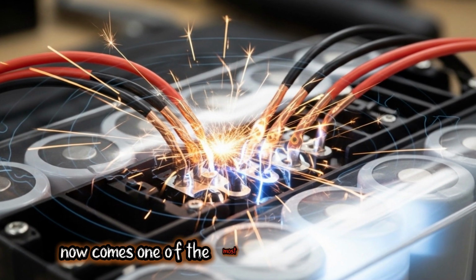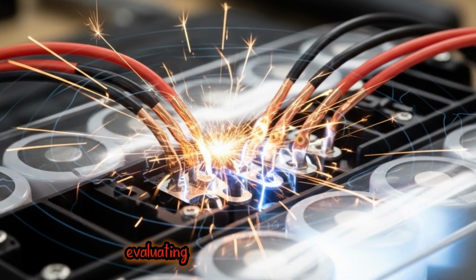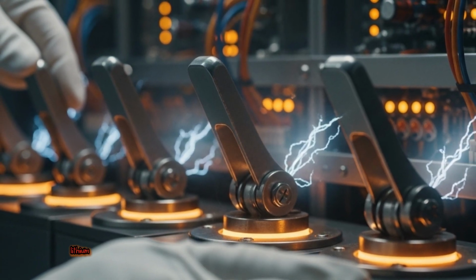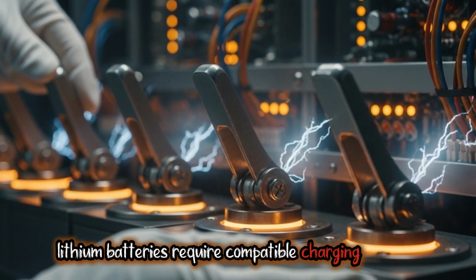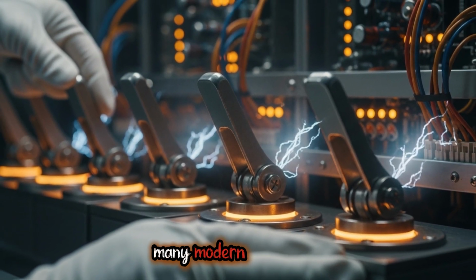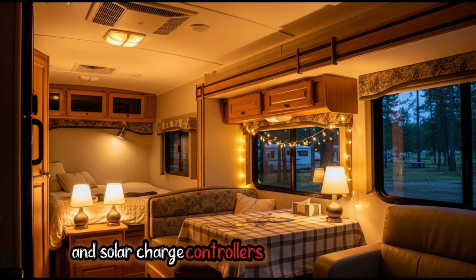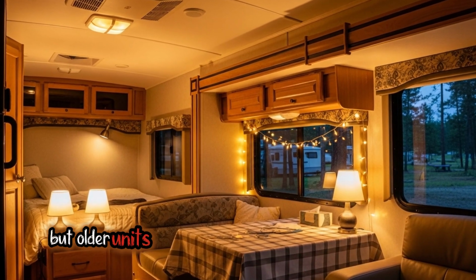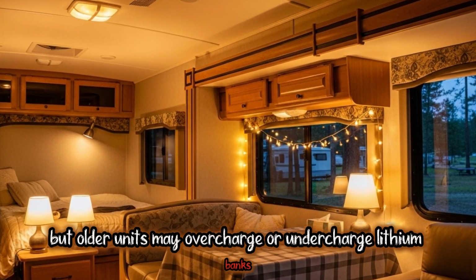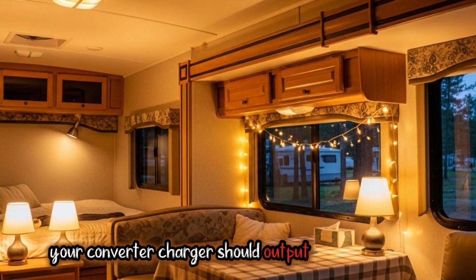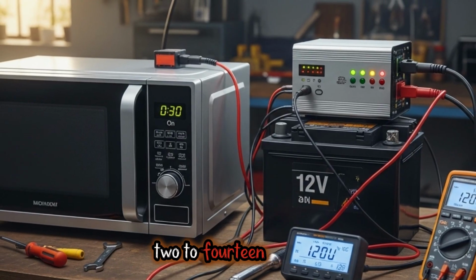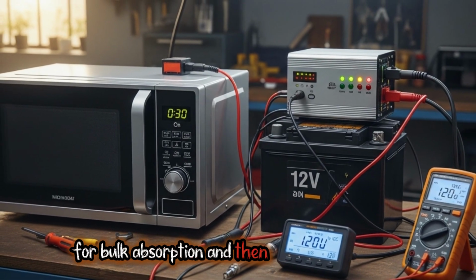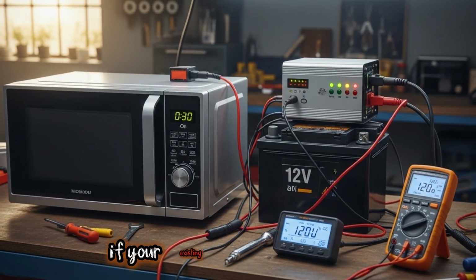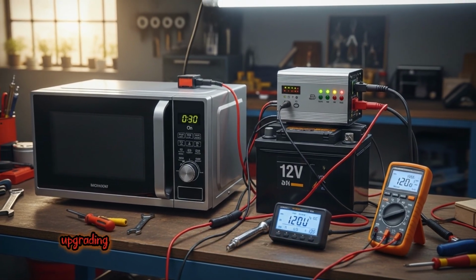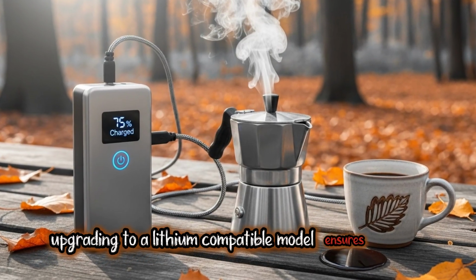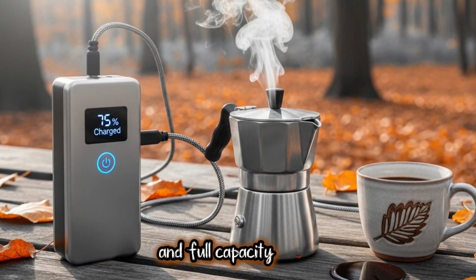Now comes one of the most important upgrade steps: evaluating your charging systems. Lithium batteries require compatible charging profiles. Many modern converters and solar charge controllers have lithium settings, but older units may overcharge or undercharge lithium banks. Your converter charger should output around 14.2 to 14.6 volts for bulk absorption and then stop or float lightly. If your existing converter is outdated, upgrading to a lithium-compatible model ensures proper charging and full capacity usage.